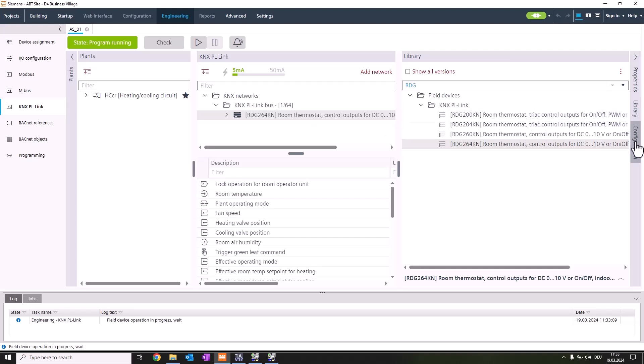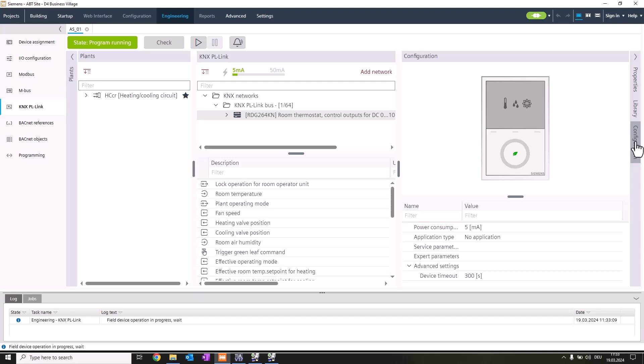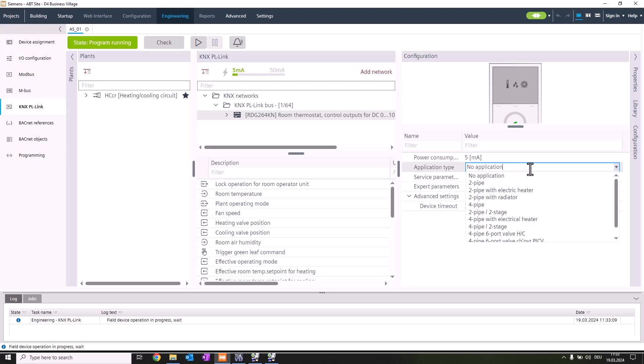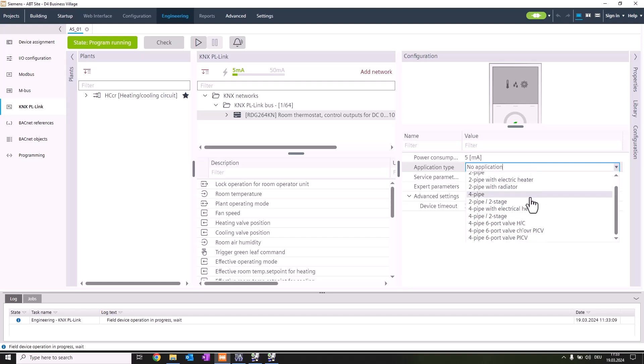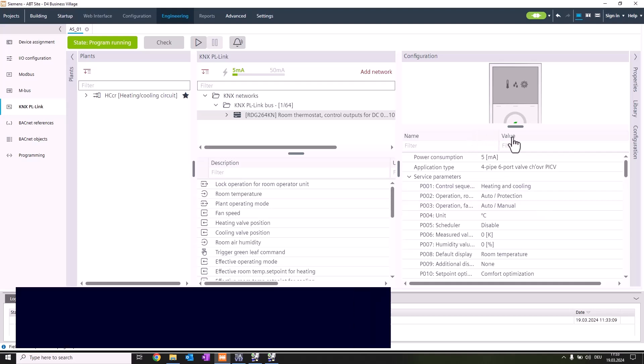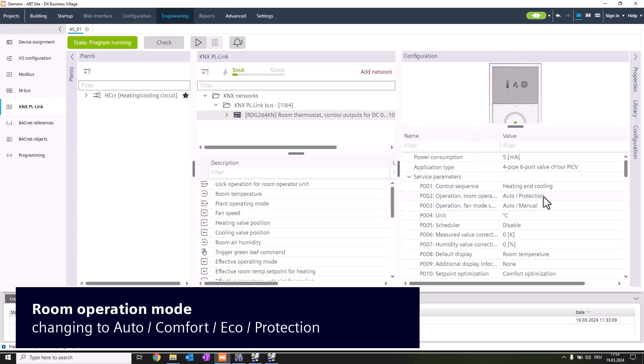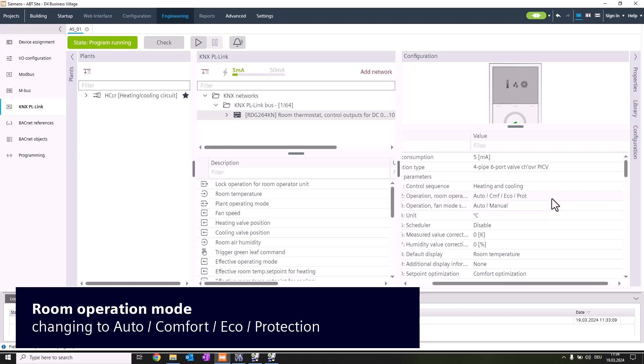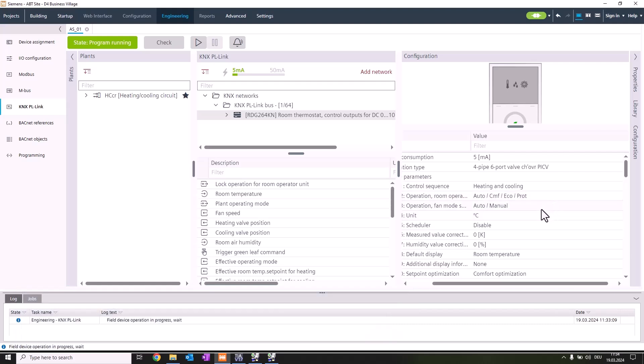We're switching to the configuration editor and the next step is to select an application type. In our project we want to use a 4-pipe 6-port valve with changeover for the PICV. In the application configuration we have to adapt certain parameters according to project requirements. For example, the room operating mode we're going to change to auto, comfort, economy, and protection, so we're more compatible to the Desigo system.